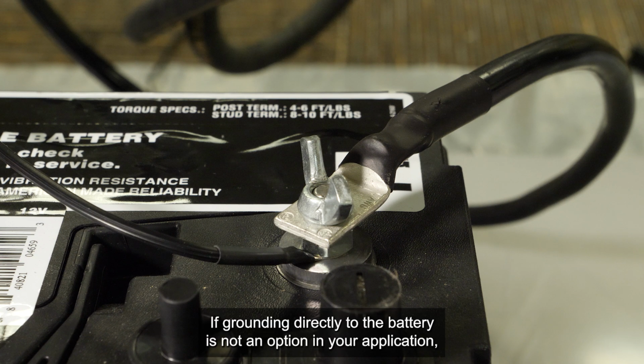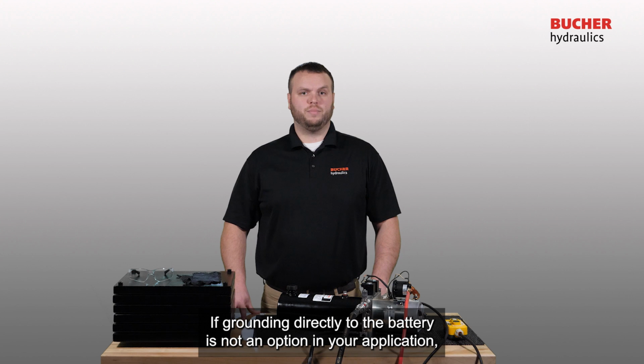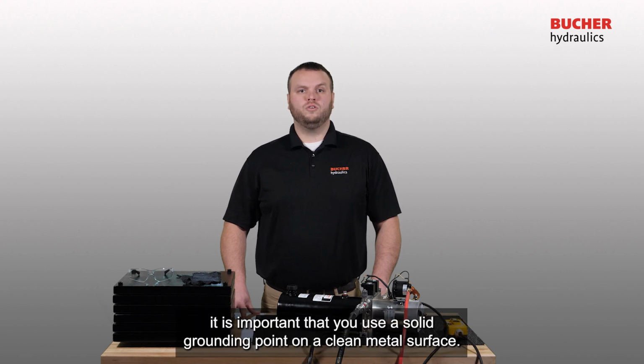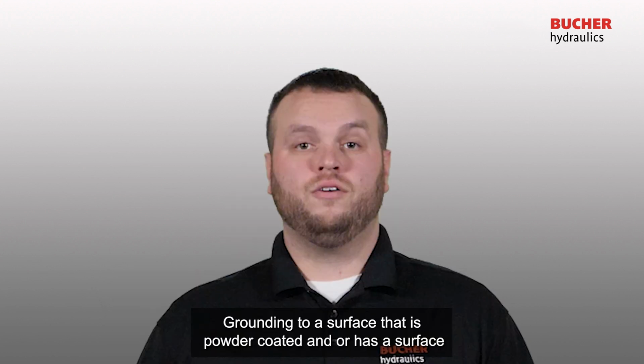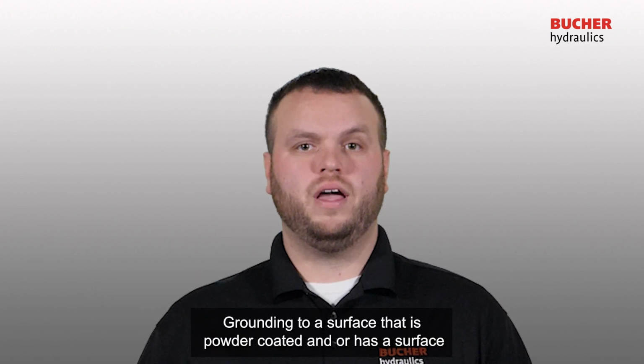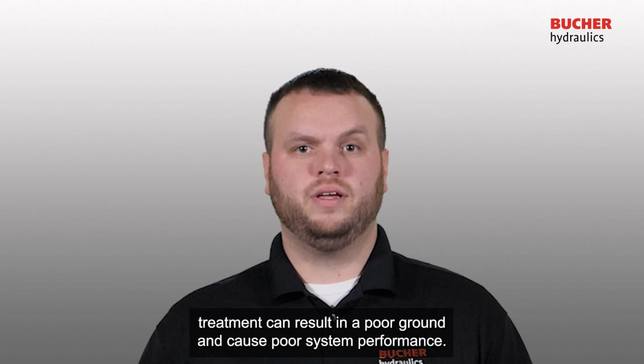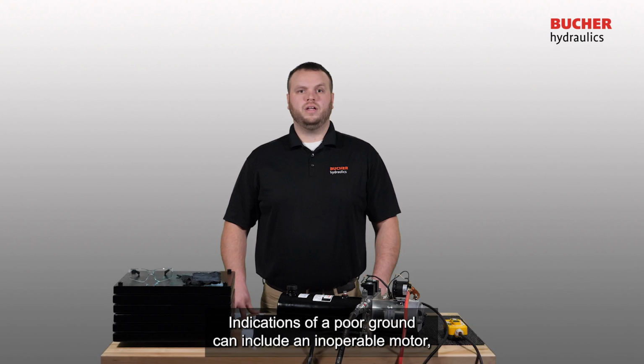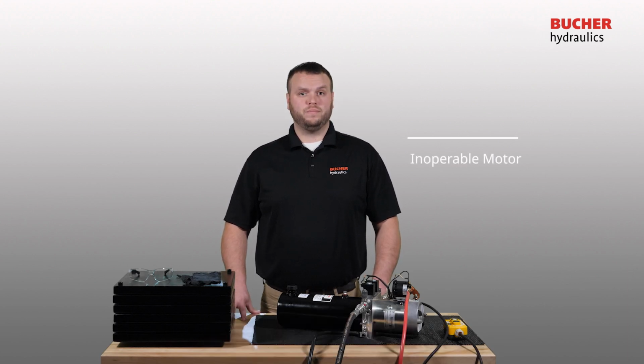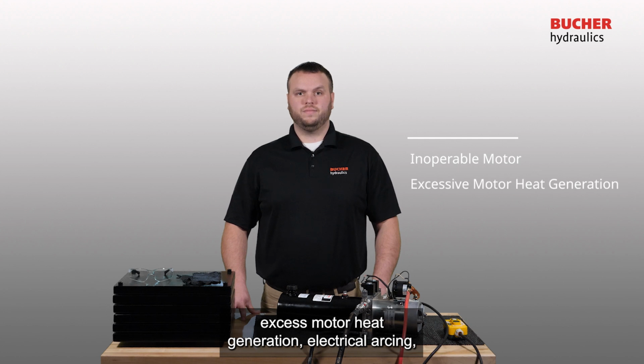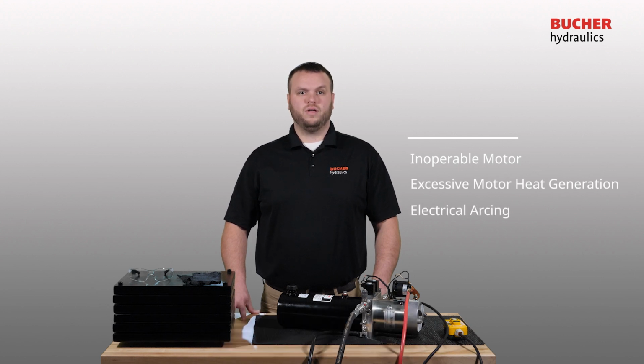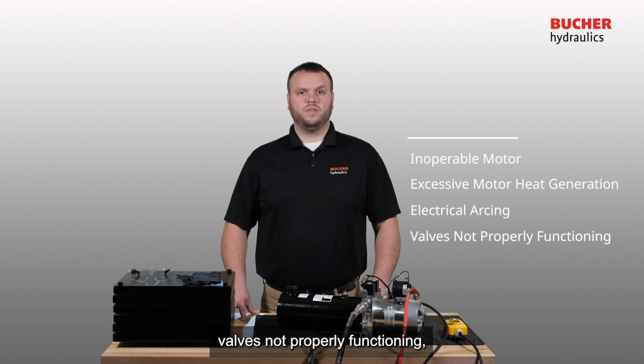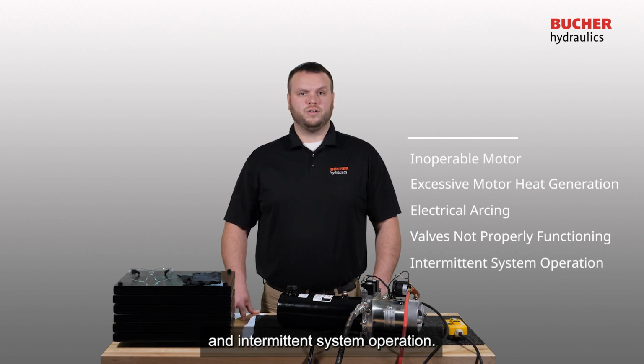If grounding directly to the battery is not an option in your application, it is important that you use a solid grounding point on a clean metal surface. Grounding to a surface that is powder coated and/or has a surface treatment can result in a poor ground and cause poor system performance. Indications of a poor ground can include an inoperable motor, excess motor heat generation, electrical arcing, valves not properly functioning, and intermittent system operation.